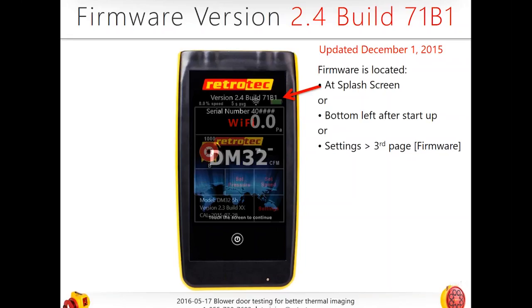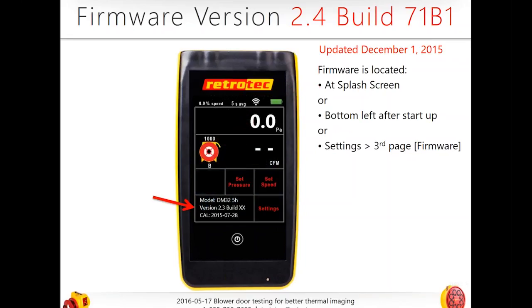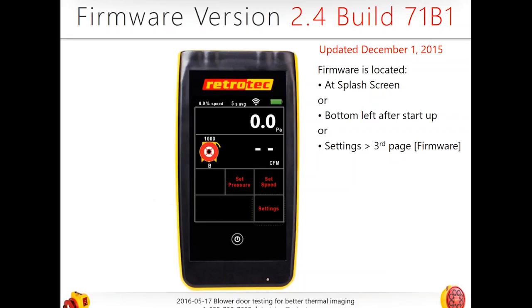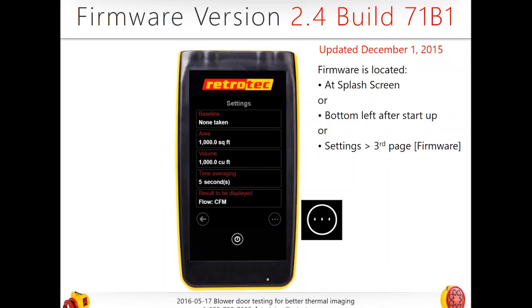How do you know if your firmware is updated? As soon as you turn it on at the splash screen, you'll see your serial number and then the version or build. Or at the bottom left after startup, or in settings on the third page, you'll see your firmware. Your version and build should be 2.4, build 71B1. You'll also see your calibration date there — that is specific to the DM32, not the DG700.